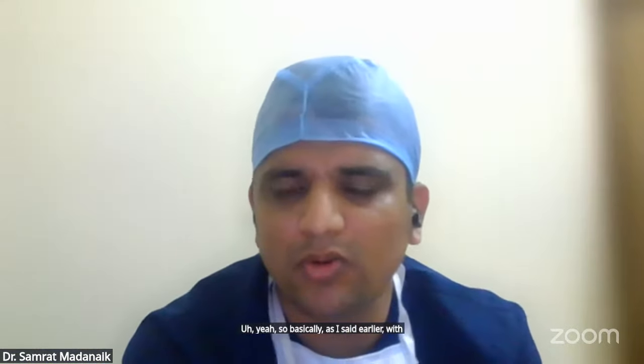One more question is coming from ophthalmic surgeries. What precaution is to be taken for eye surgery, especially retina, because they can't use bipolar cautery at that time? As I said earlier, with monopolar cautery, try to avoid bursts. Try to keep the energy as low as possible. Try to keep each burst as short as possible, less than 1 second if possible. And the gaps between cautery bursts should be more than 10 seconds. That would be the ideal way to go about it.